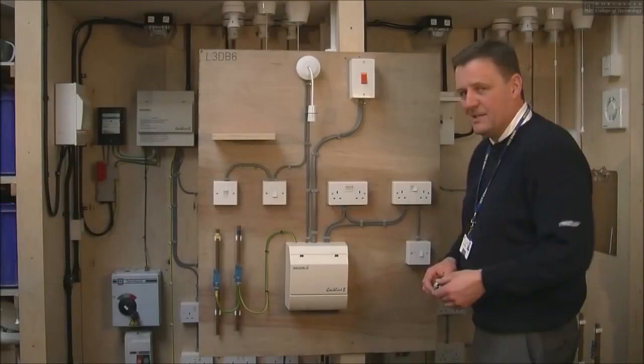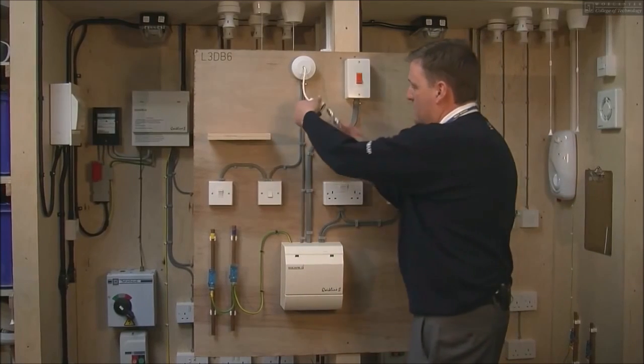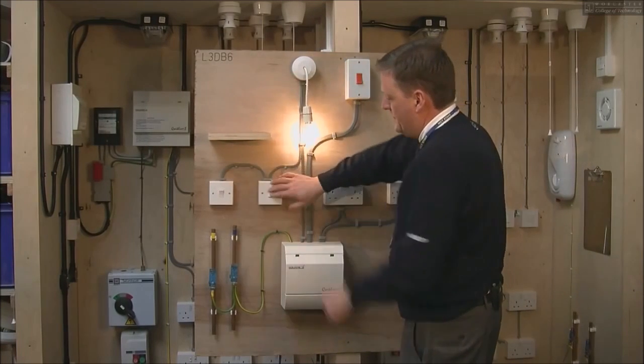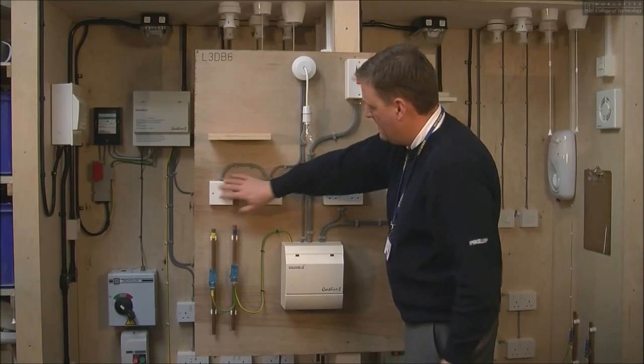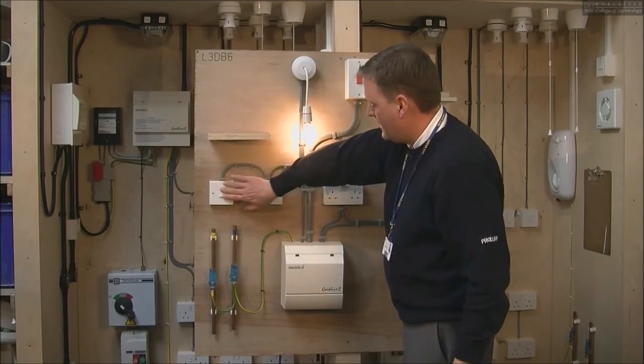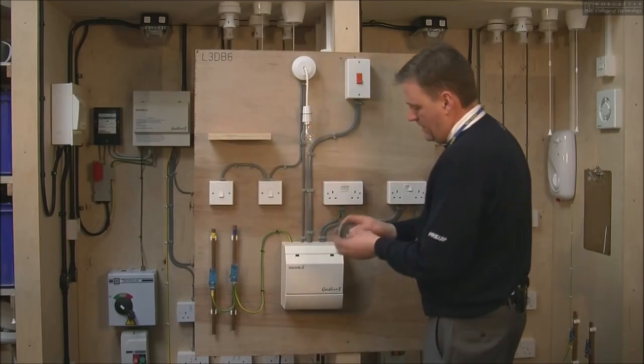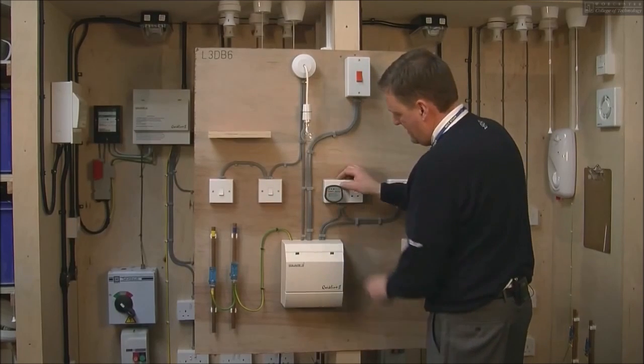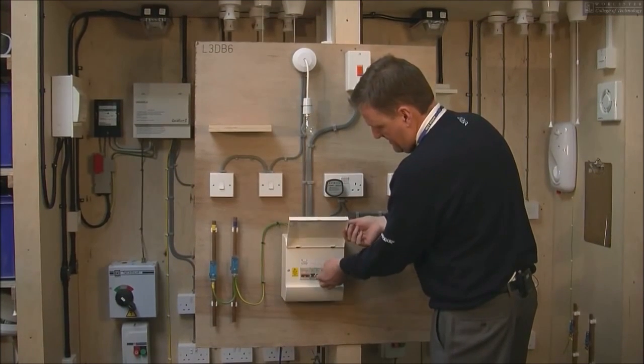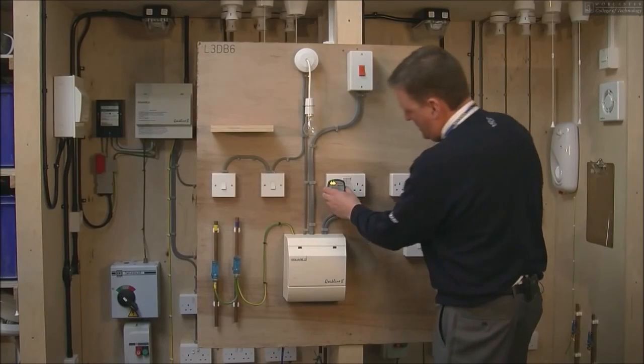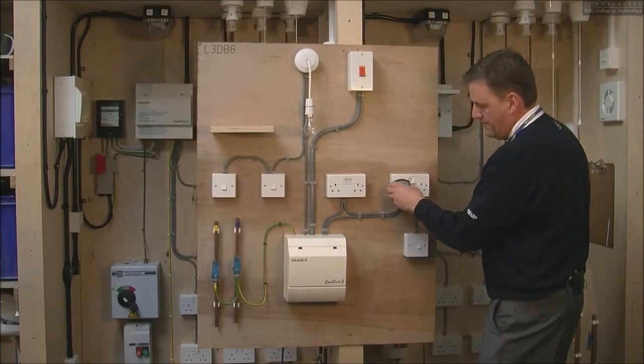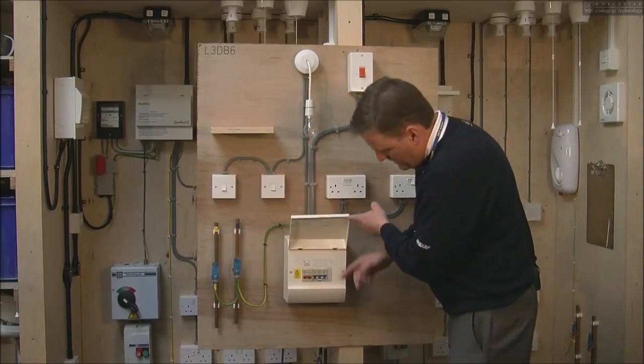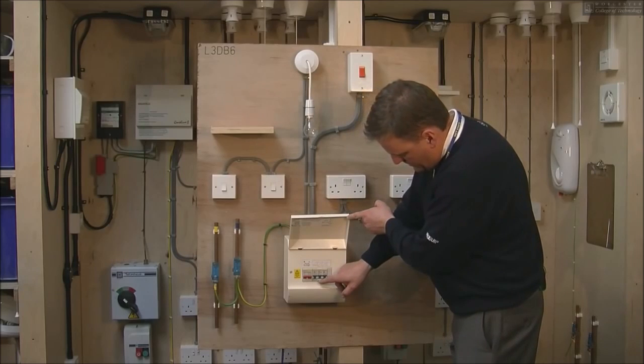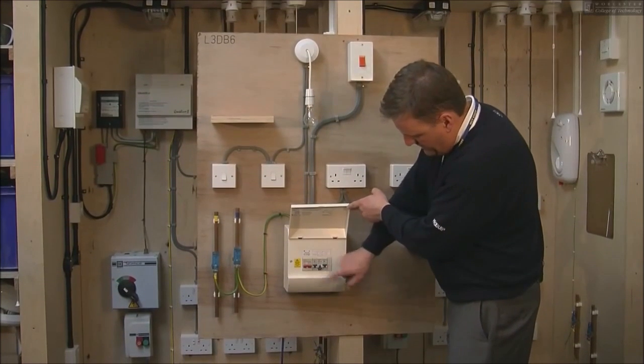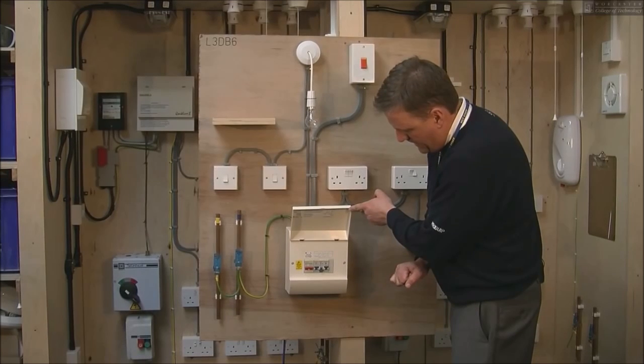The final test we do is the functional test, in which we simply insert the lamps, check that the light's working correctly. I've got a little plug-in tester, and again this just indicates that the sockets are all working. And the final test we do for functional testing is we just press the test button on the RCD to ensure that that works correctly.